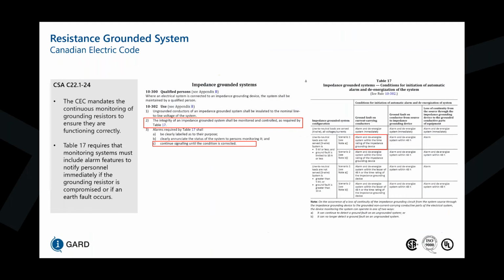Now, in the Canadian Electrical Code in Section 10, Grounding and Bonding, in -300, they have clauses for impedance grounding systems. And it says that the integrity of an impedance grounding system shall be monitored and controlled as required by Table 17. And we have to continue signaling until the condition is corrected.